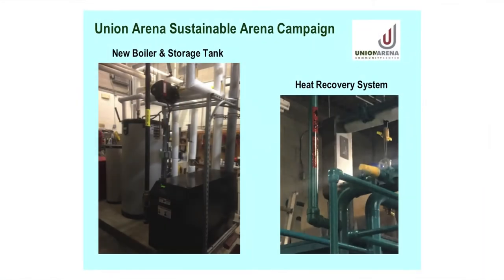We did do a couple of things out of phase four, and one of them was a heat recovery system. So we get an enormous amount of heat off the compressors. That's why there's a cooling tower on the roof, which is sort of standard for a rink. But you have to say, if you've got a cooling tower on the roof, that means you're sending heat up into the atmosphere, literally warming the globe.